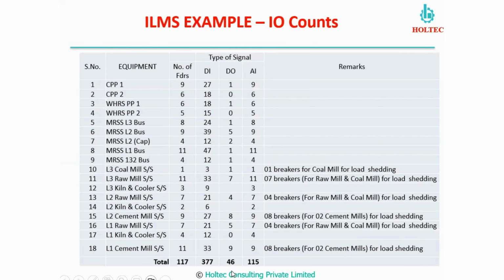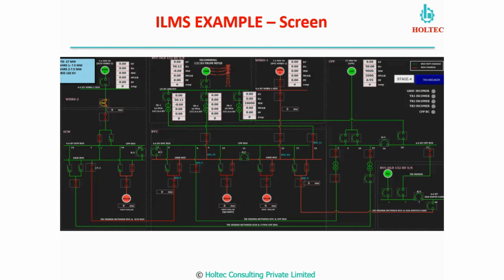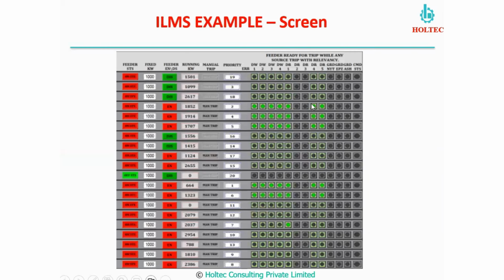This is the dashboard which shows the SLD in our ILMS system screen, where we can see the power flow, various parameters, the status of the breakers, and the status of the other equipment and the tie breakers also. This is a screen of the ILMS system where you can have a priority table. So you can prioritize the load shedding loads based on your requirements in real time. You can change it at any moment of time.